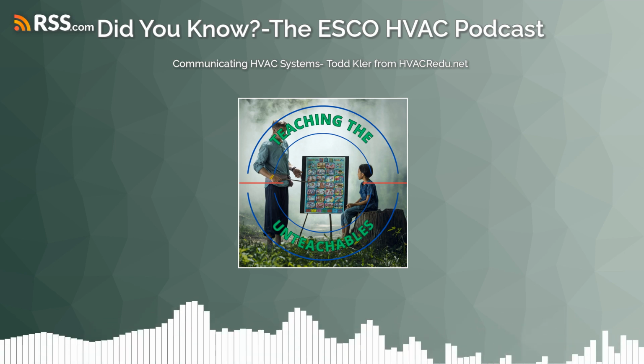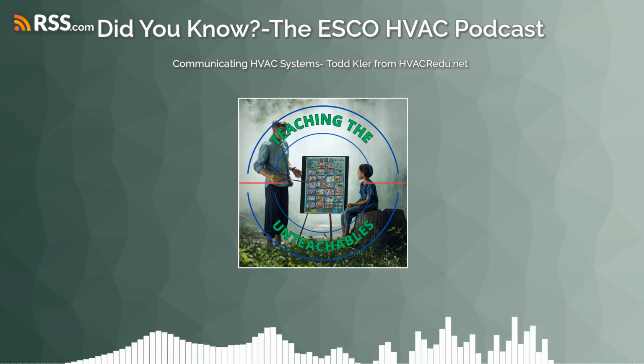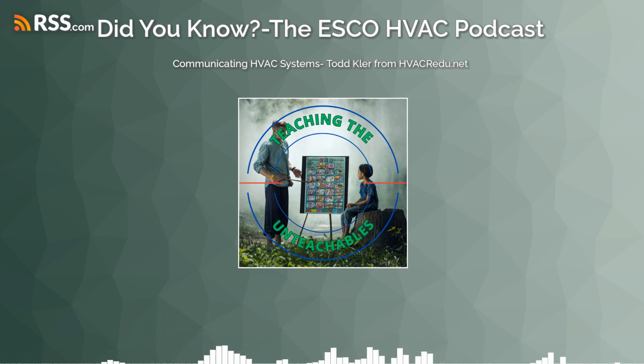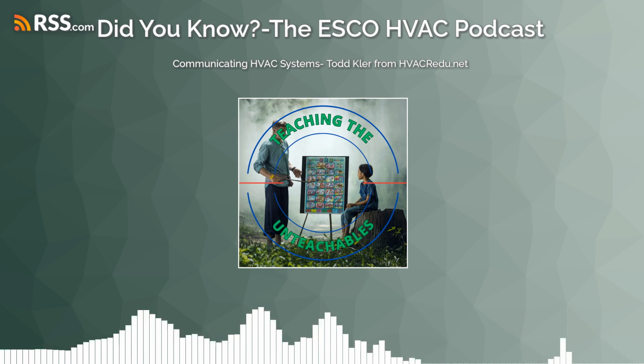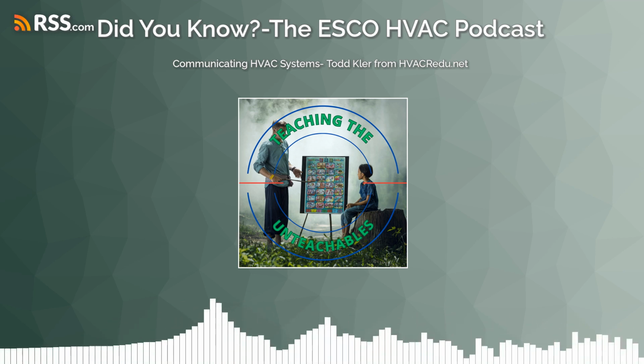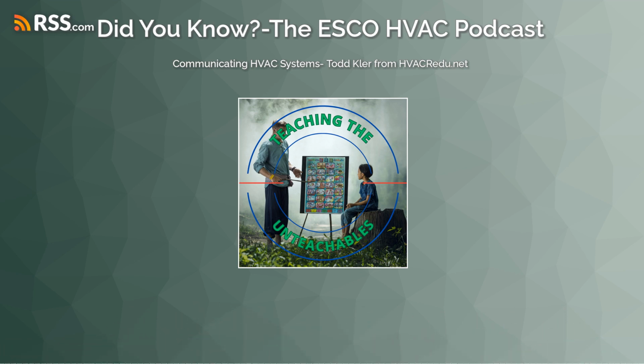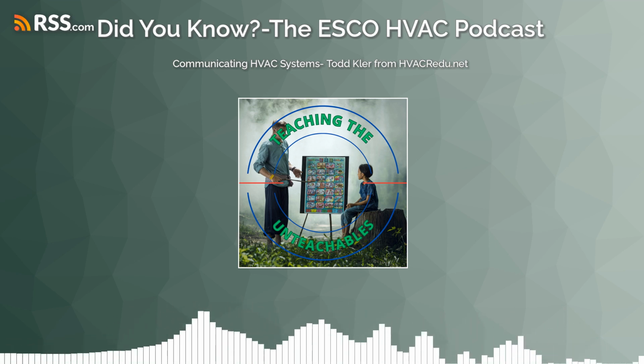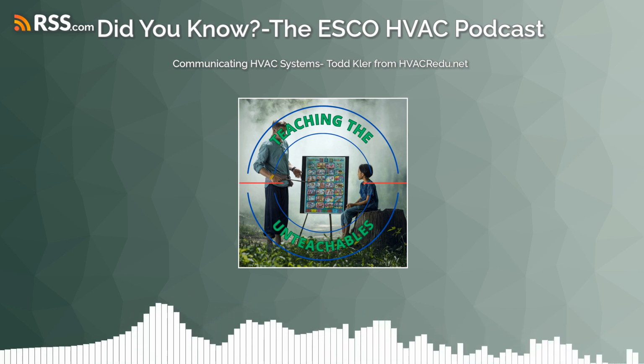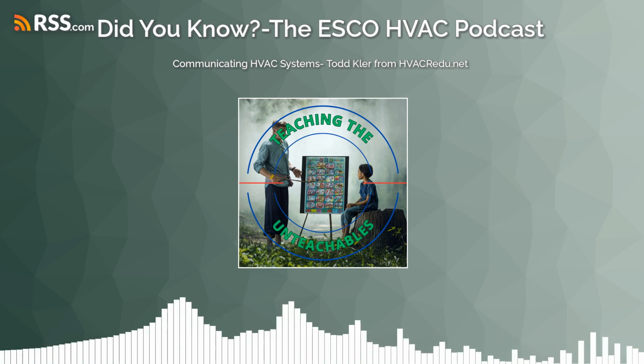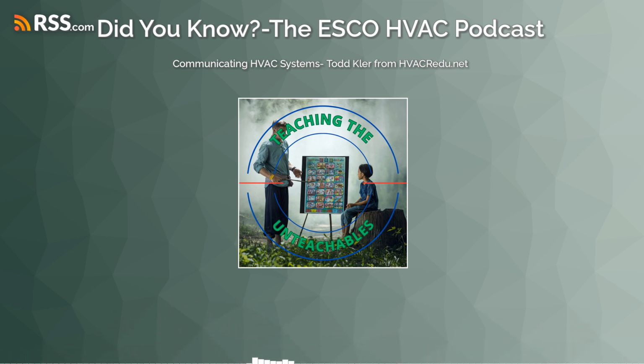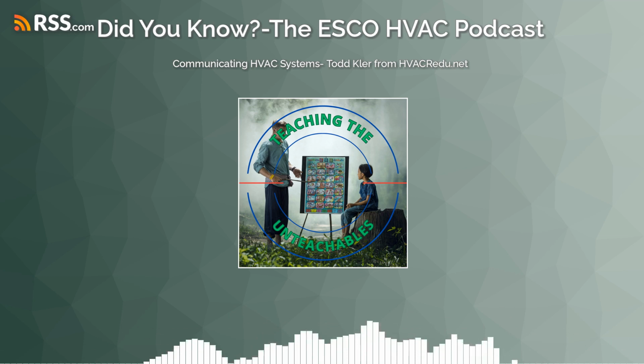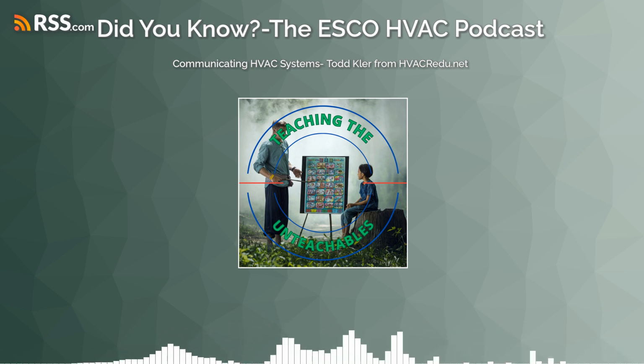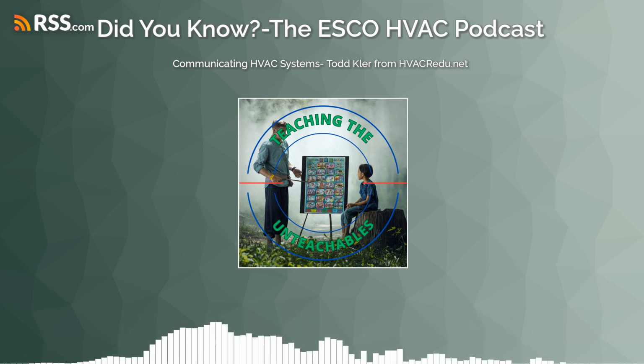All right? Let's start at the indoor unit, Todd. All right, let's go to the indoor unit. And interesting that everything's tied back to the indoor unit on these unitary systems. Yeah. It'll be completely opposite when we get to our ductless. Absolutely. But on all of our unitary, our primary DC voltage is coming from that indoor control board. Yes. So let's look at this indoor control board. This one's using a smart hub because it's connecting another component to it. But we can even talk about the smart hub if we needed to. But what do you see at that indoor unit? Do you see 4 wires? Yeah, I do. I got an R, I don't see a common. So the R and the common, I imagine, would be 24 volts, and the 2 in the middle, I see a negative and a positive. I can't read what they are. They call it I, but it's I positive and I negative. So there you go.